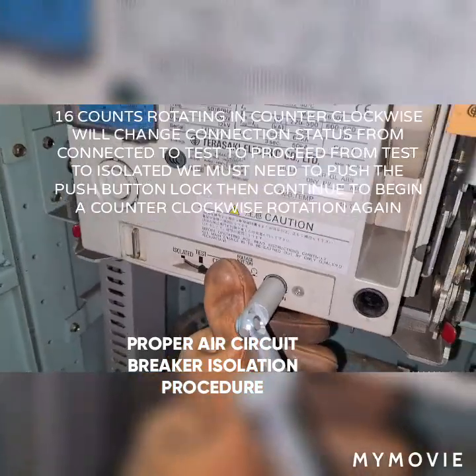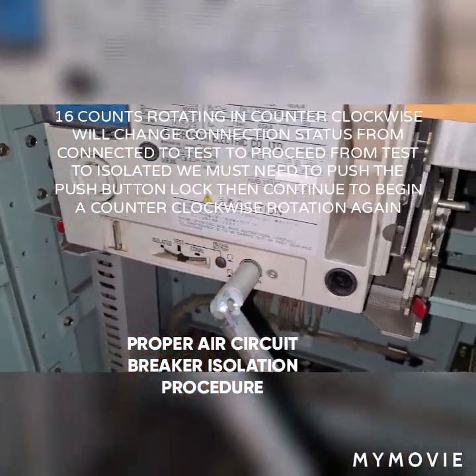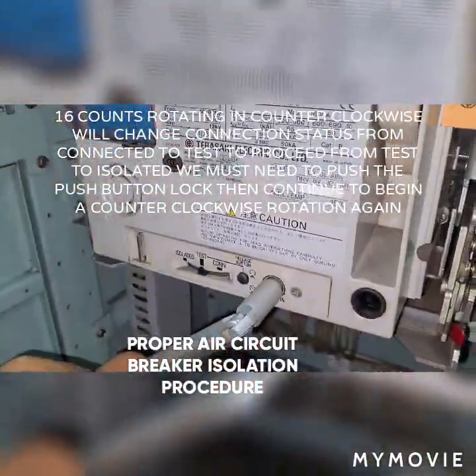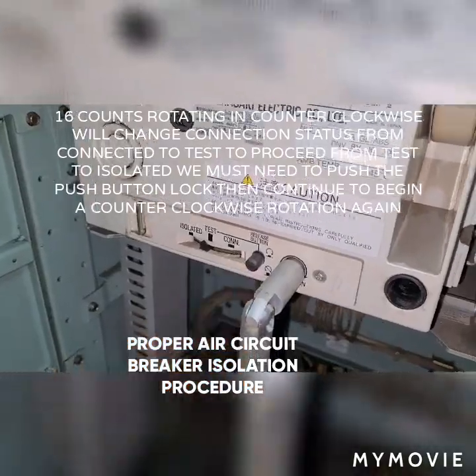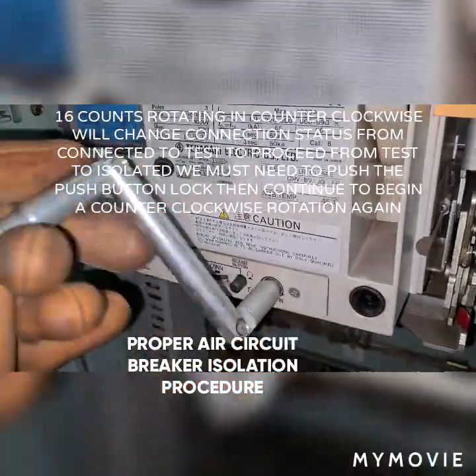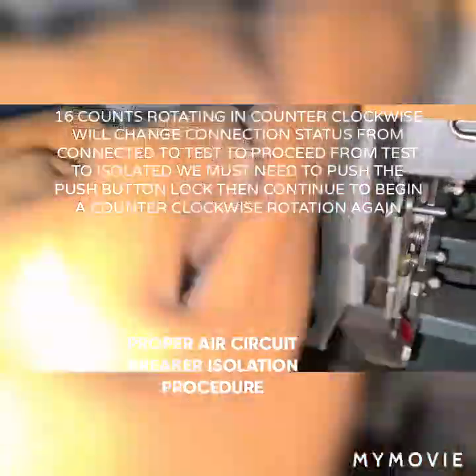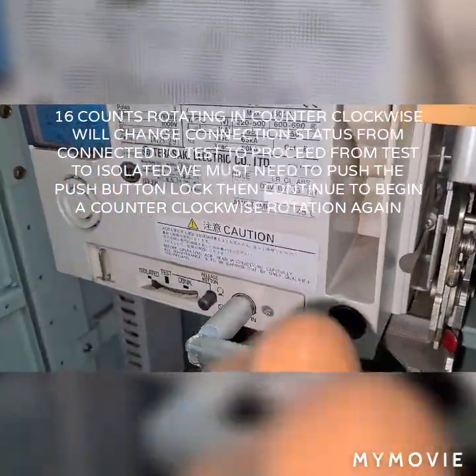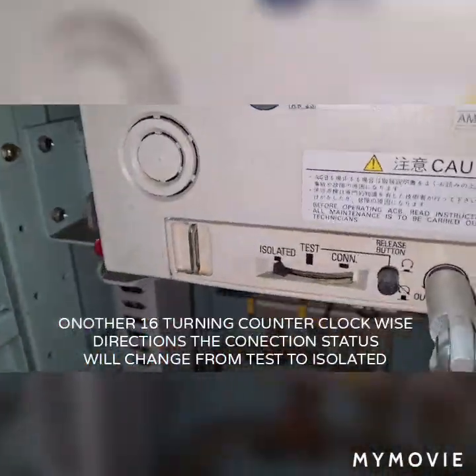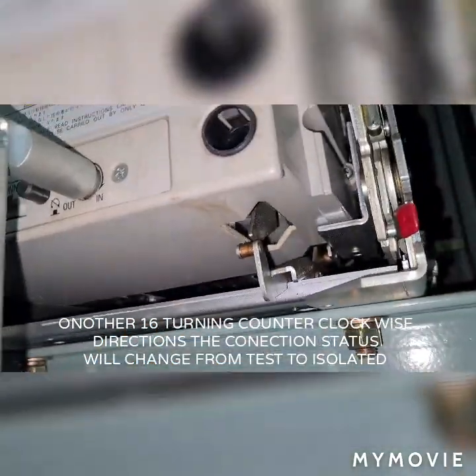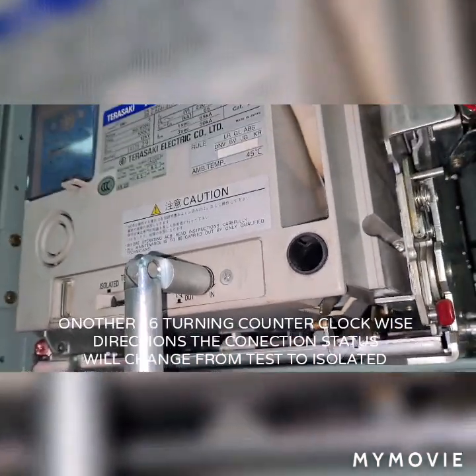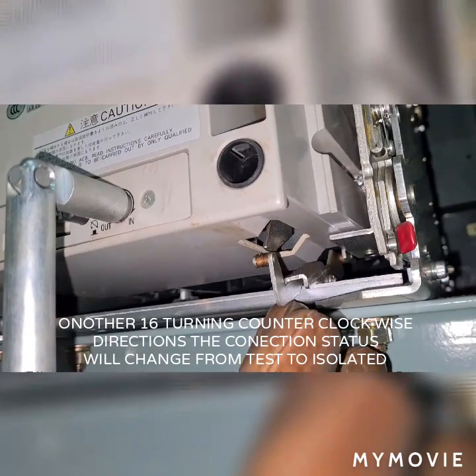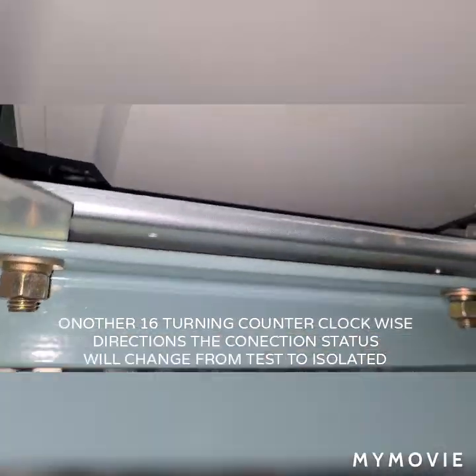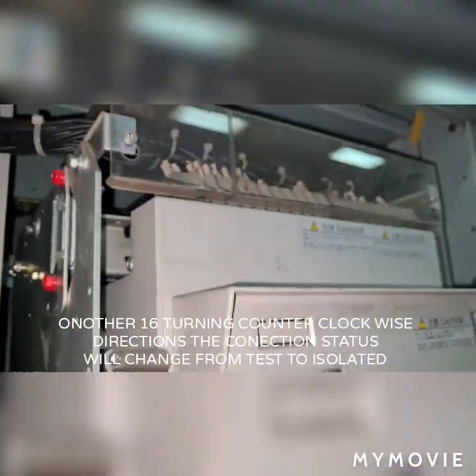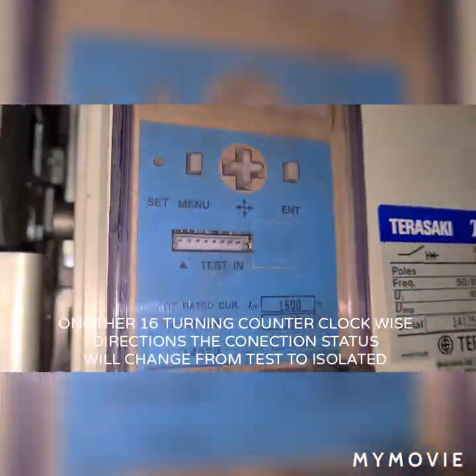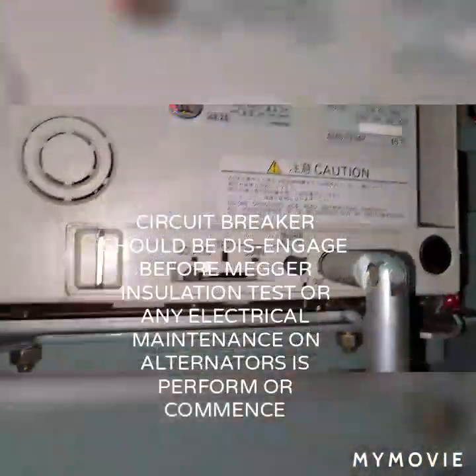So guys, as you will find, I already made 16 turns. I just push the push pin and I'm going to continue rotating again about 16 times, so we are able to change the state of the connection setting from test to isolated. As you can see on the connection setting, the circuit breaker is already released. Aside from that, there is also a mechanism at the bottom part of the circuit breaker which is already released, and that is another thing that you need to check and verify, that the circuit breaker is already isolated.